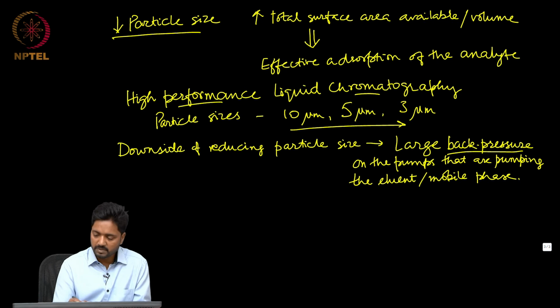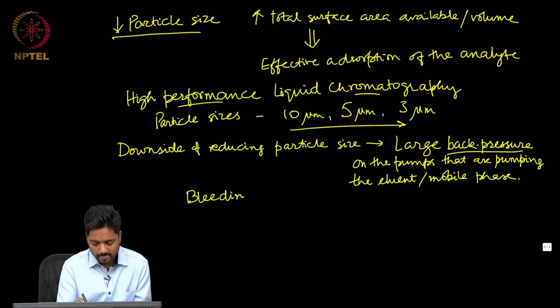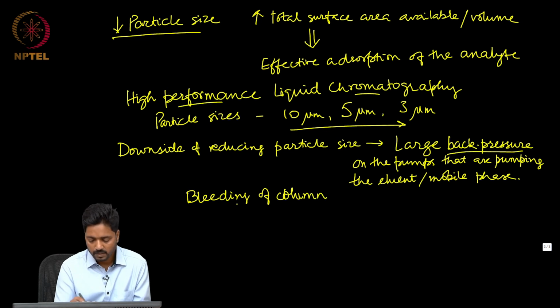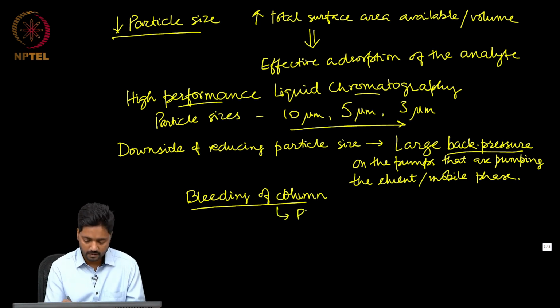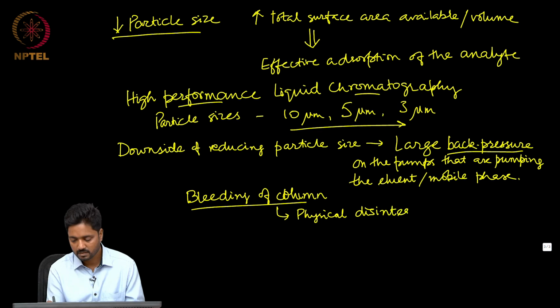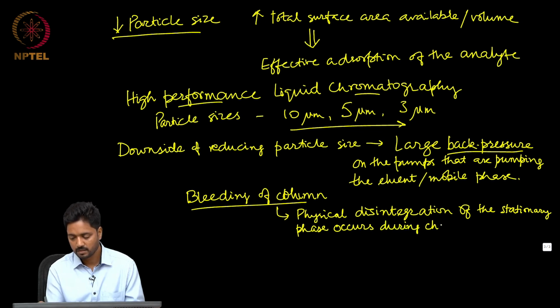So, while there is a very clear interest in reducing the particle size, the back pressure becomes a very important problem. Another problem that comes here is that of the bleeding of column. Now, this is where the physical disintegration of the stationary phase occurs during chromatography.